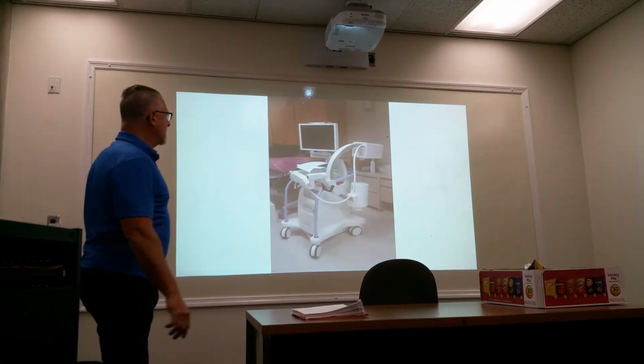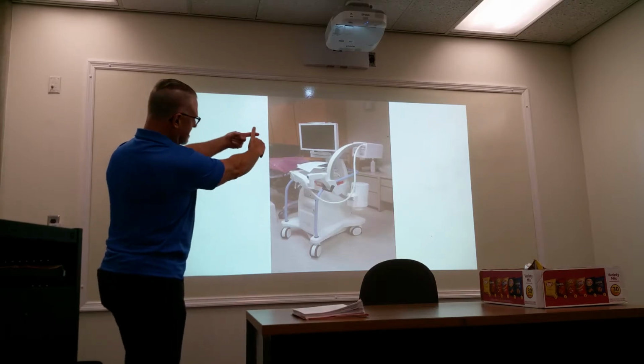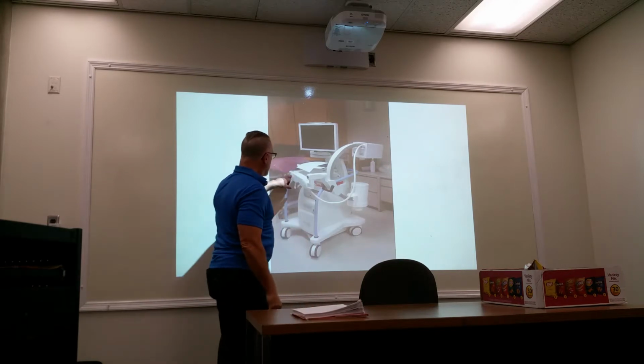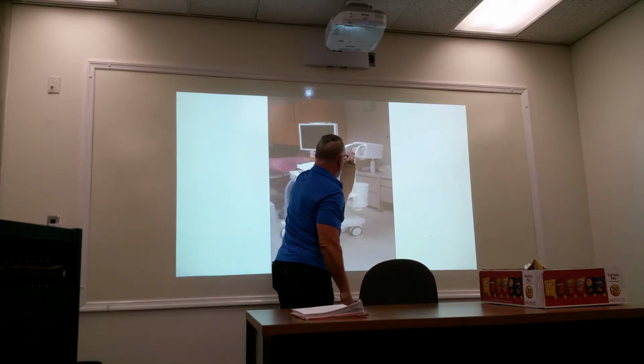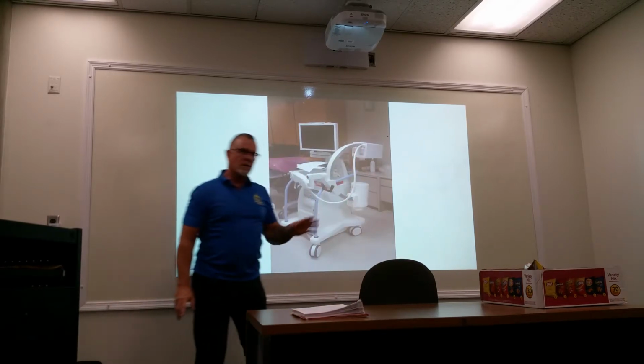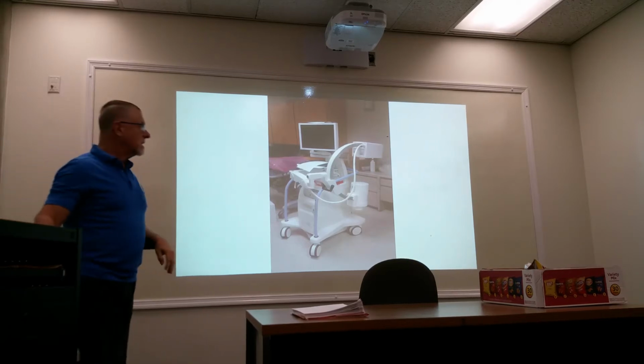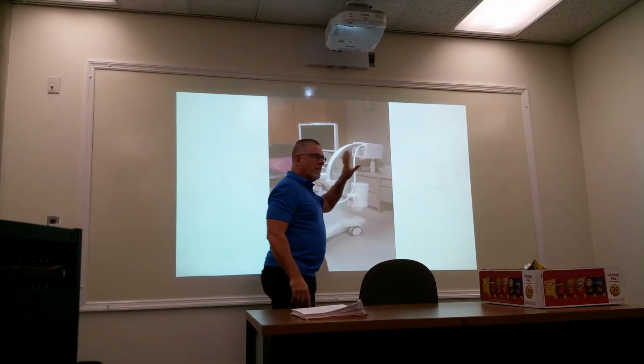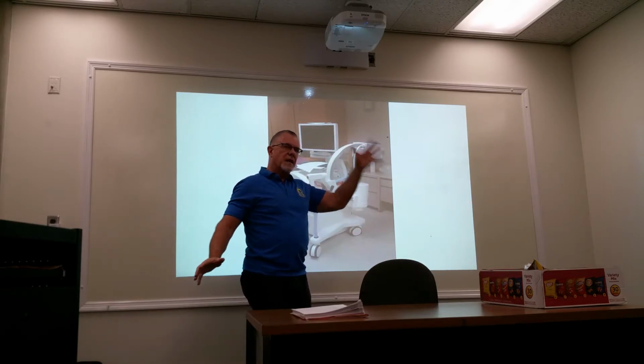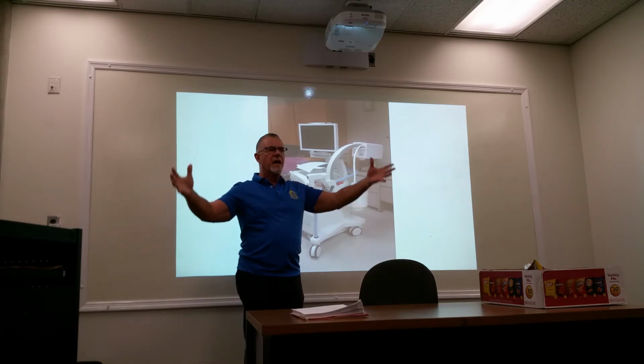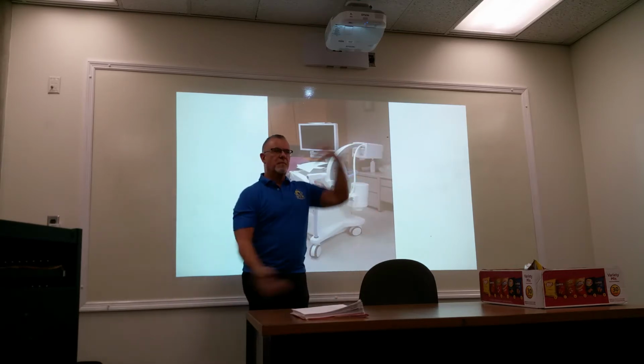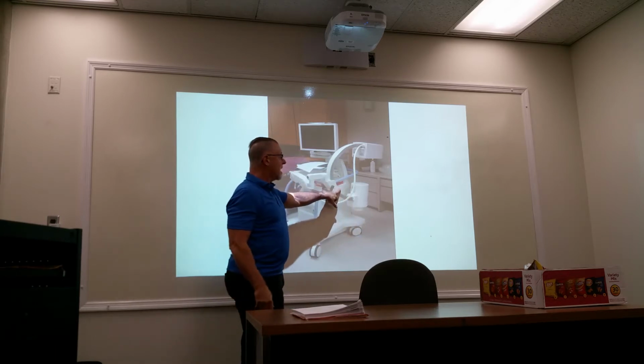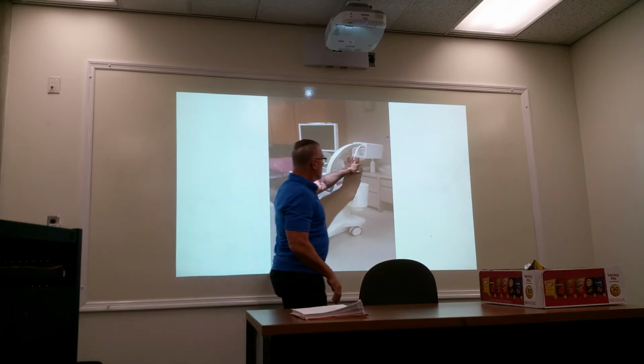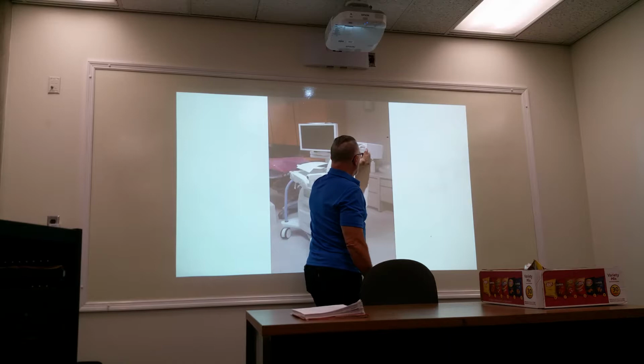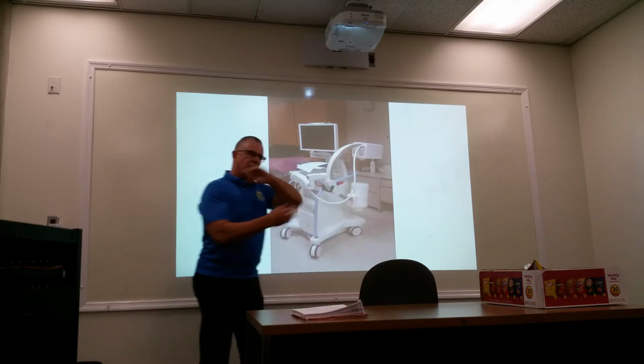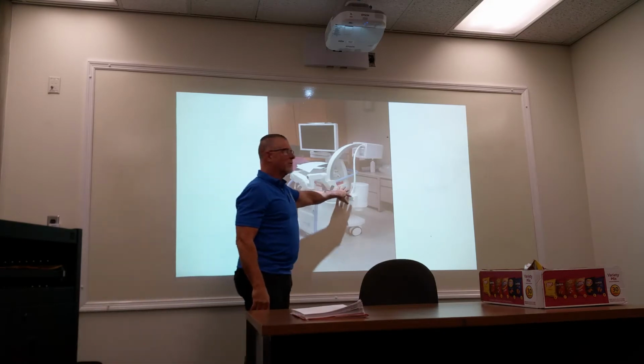This is the infamous mini C-arm. That's a fluoro scan. Every hinge that you see is manually locked. And the thing about this that really irritated me, and we reported it to the FDA, I don't think they really did anything, is that in your regular full-size C-arms, the image detector side and the tube side are counterbalanced. So if you unlock it, it's not going to go flipping around someplace. This little guy, if you unlock it and you don't know what you're doing, it's going to flip. Because for this one, the tube's up here, it's a smaller tube. The high voltage is up here, so this weighs a lot more than this, and it'll go flipping around. So be really, really careful.